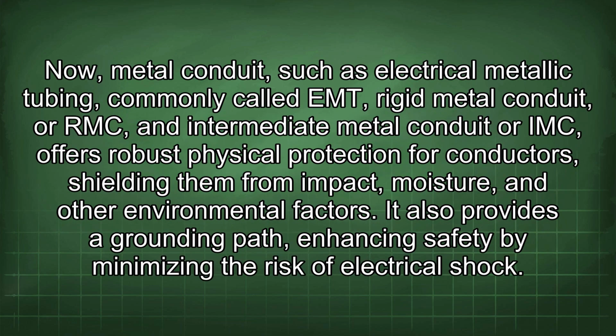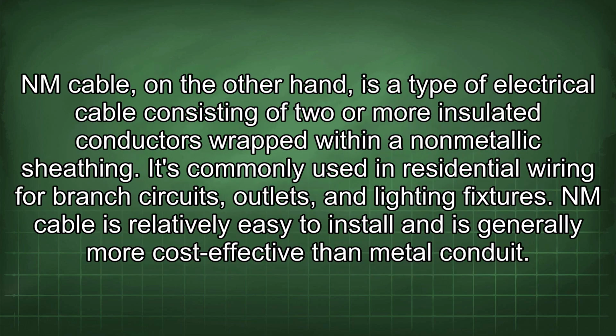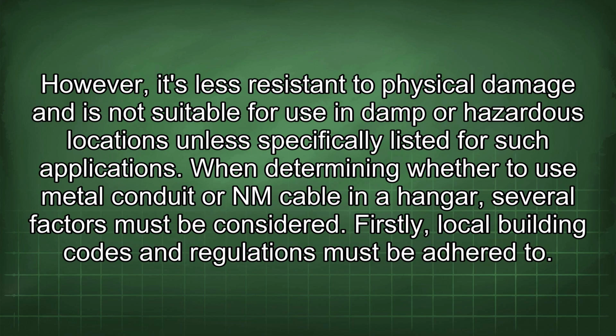Now, metal conduit, such as electrical metallic tubing, commonly called EMT, rigid metal conduit, or RMC, and intermediate metal conduit, or IMC, offers robust physical protection for conductors, shielding them from impact, moisture, and other environmental factors. It also provides a grounding path, enhancing safety by minimizing the risk of electrical shock. NM cable, on the other hand, is a type of electrical cable consisting of 2 or more insulated conductors wrapped within a non-metallic sheathing. It's commonly used in residential wiring for branch circuits, outlets, and lighting fixtures. NM cable is relatively easy to install and is generally more cost-effective than metal conduit.